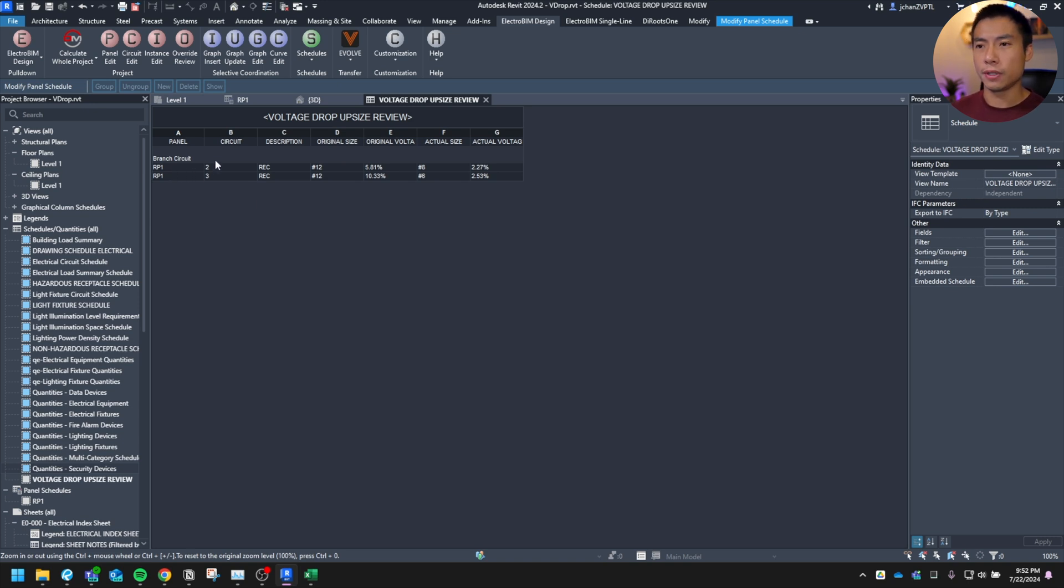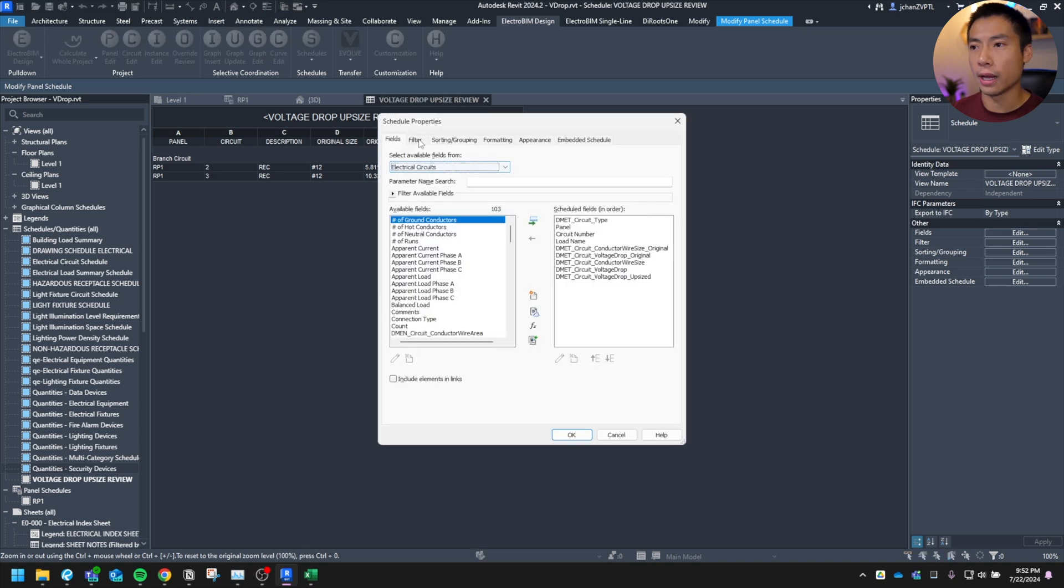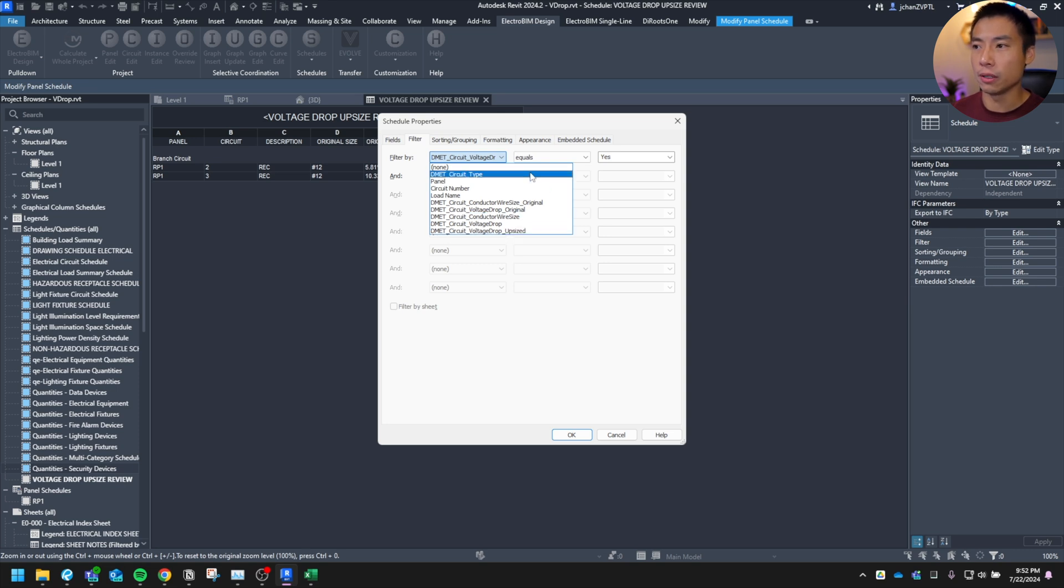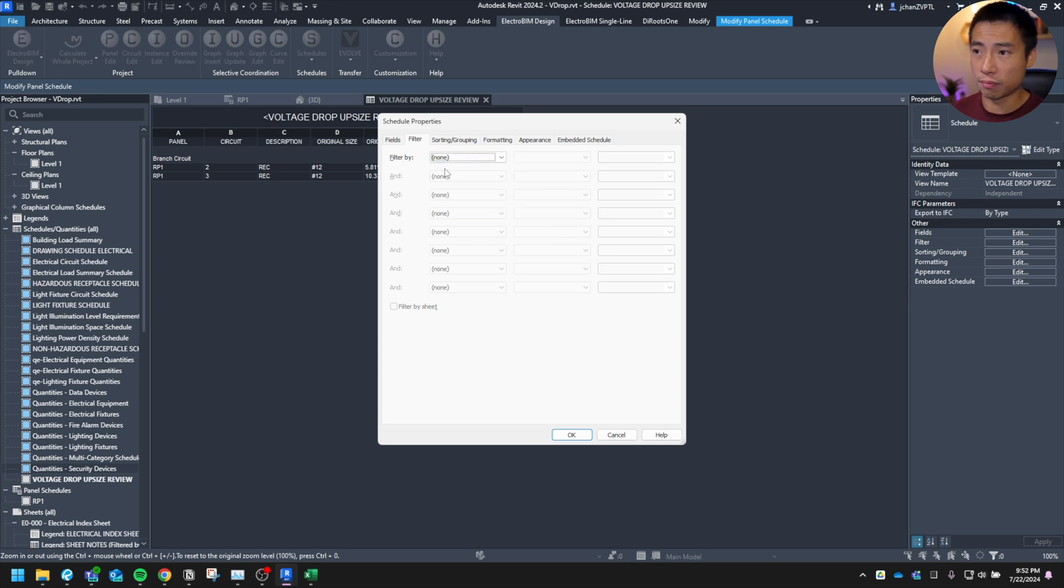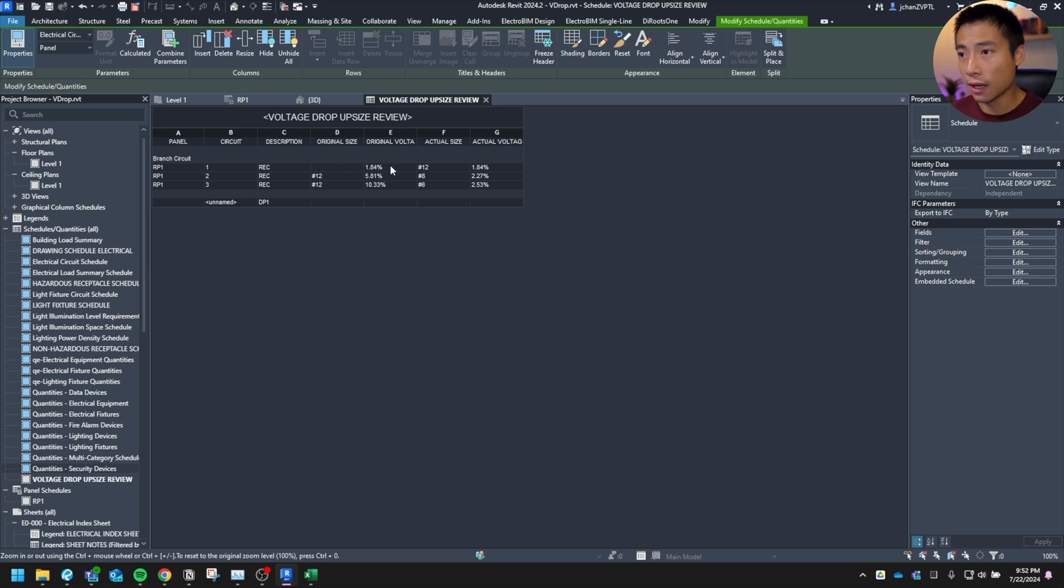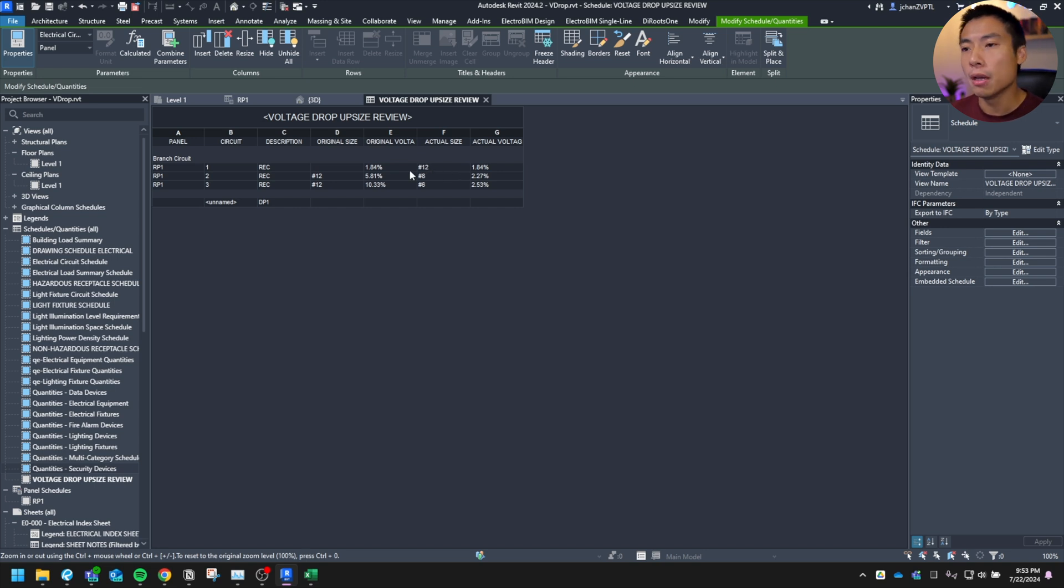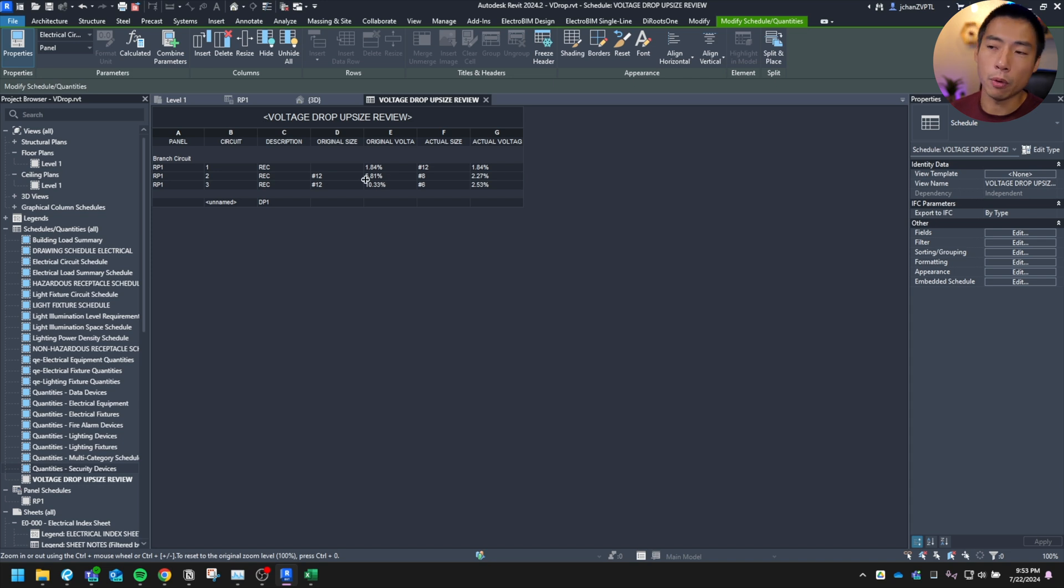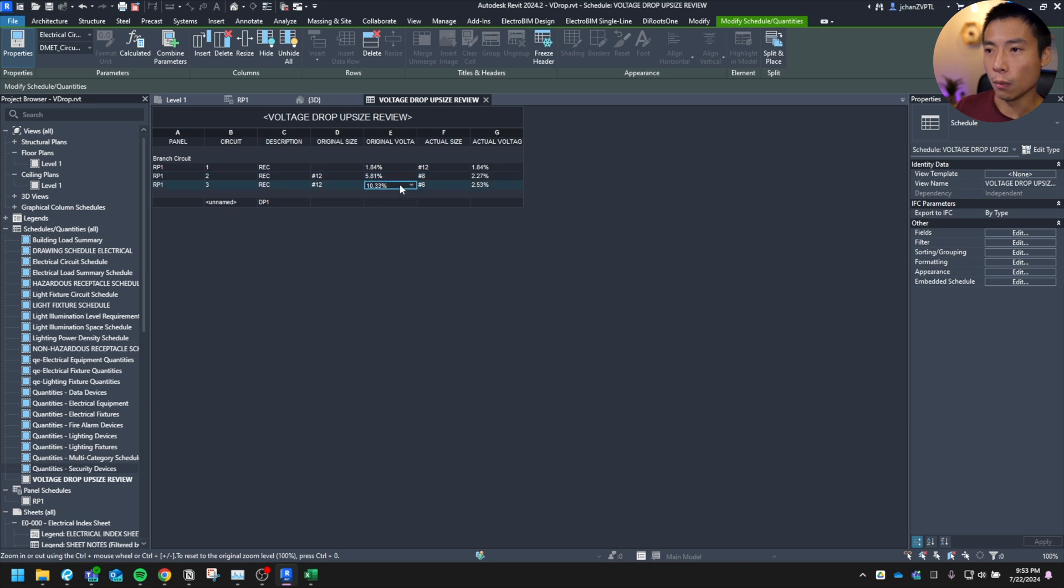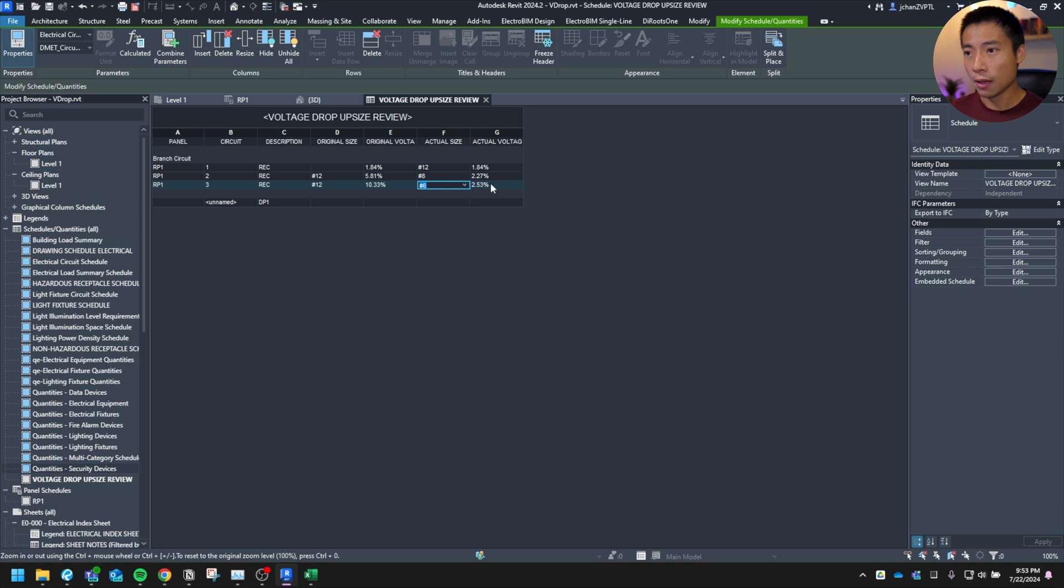You'll see circuit one's not on here. I think cause it gets filtered out because it was not upsized. So yeah, the circuit voltage drop upsize equal to yes. So if you want everything to be shown, just take out this filter, hit okay. And you can see here, circuit number one. So one was originally a 12 and then it stayed a 12. So that's why this was taken out, but you can see circuit number two, it was at 5.81% drop. If we use the number 12, it was upsized to a number eight. That gives us 2.27. And then same thing for the last one, it went from a number 12 to a number six to keep us under that 3%. Would have been a 10% voltage drop had we left it like that.